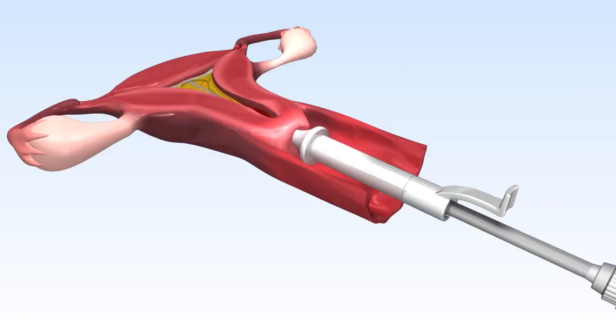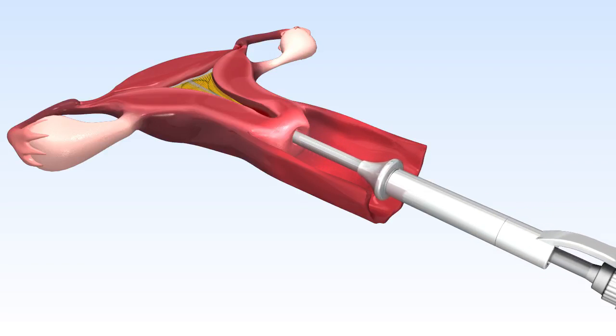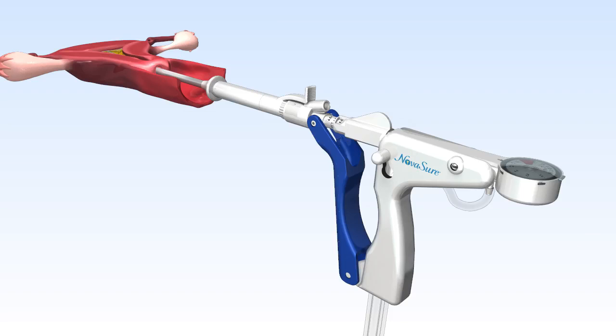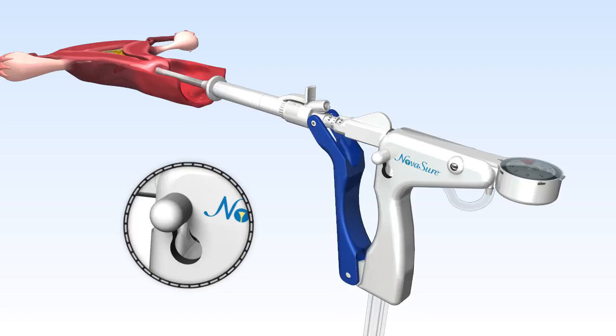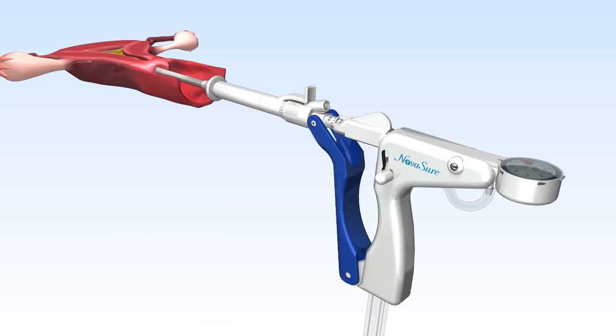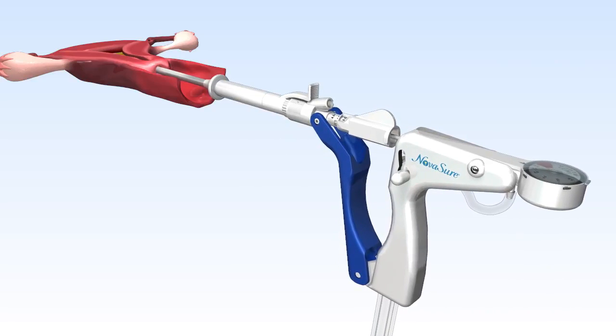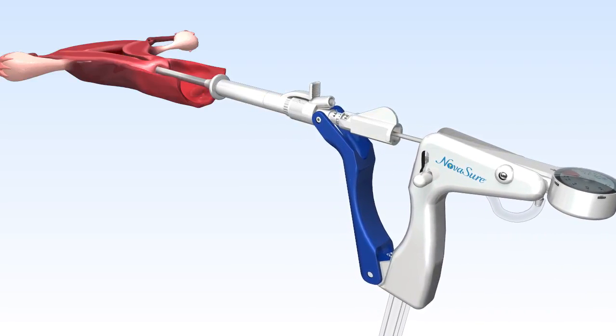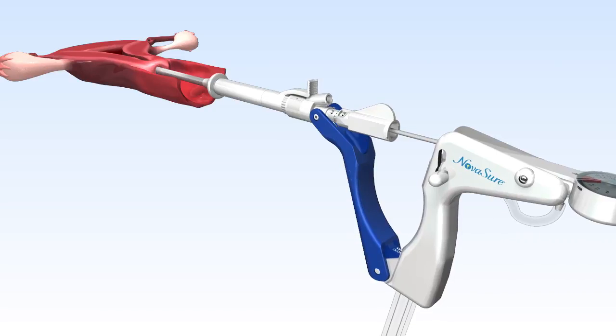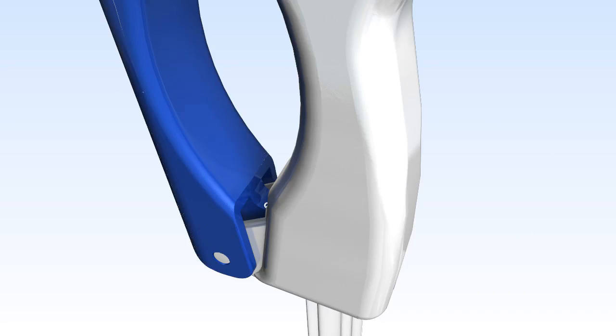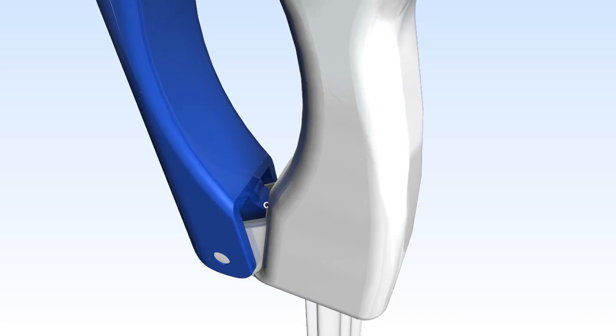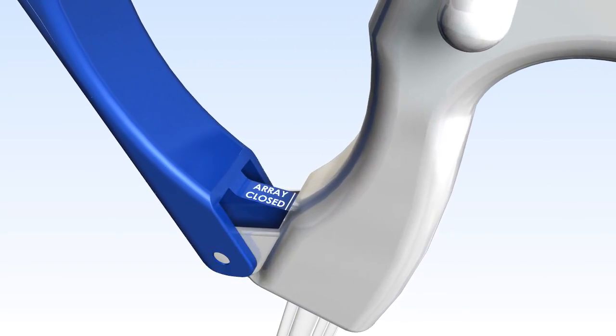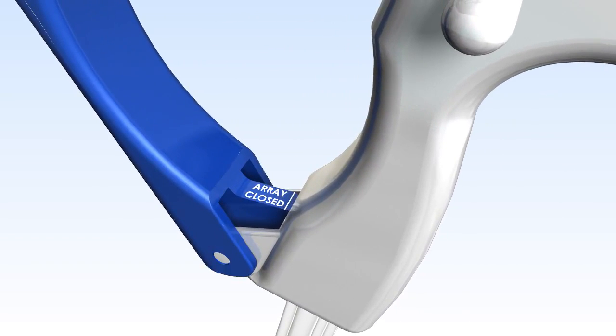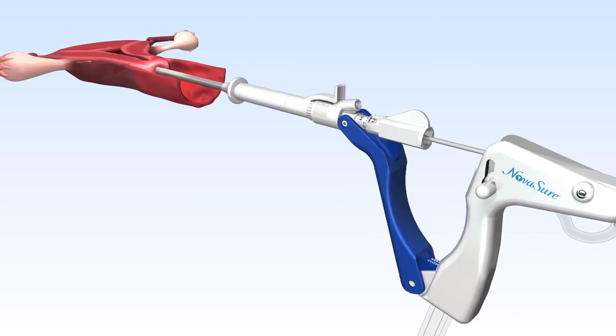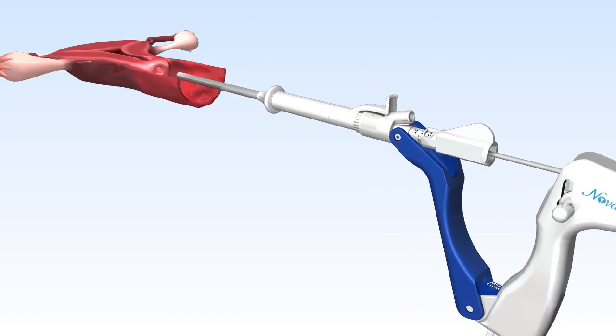Once the procedure is complete, slide back the cervical collar. Unlock the handle by depressing the button on the side of the device handle. While holding the front blue handle stationary, pull back on the rear handle to retract the electrode array into the sheath using the bow and arrow technique. The closed array indicator, located at the hinge of the front and rear handles, will read Array Closed to indicate the array has been retracted and you can remove the device.